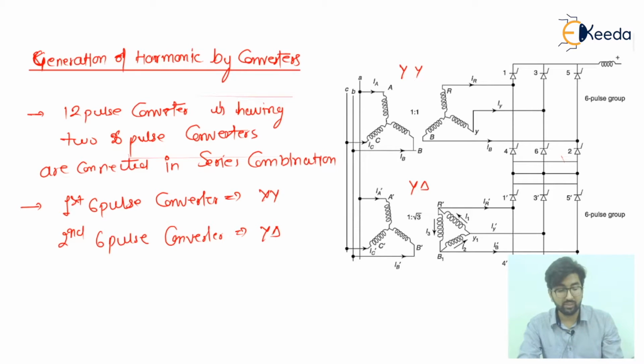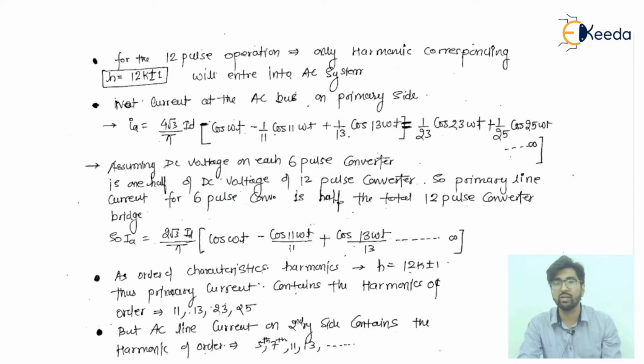Okay, so we will proceed with some of the points which are listed here, that is for the 12 pulse converter. If we talk about the 12 pulse converter or its operation, the only harmonics corresponding to the 12 pulse converter are of the order 12k plus minus 1. Please remember this, this is 12k plus minus 1, and it will enter into your AC system.